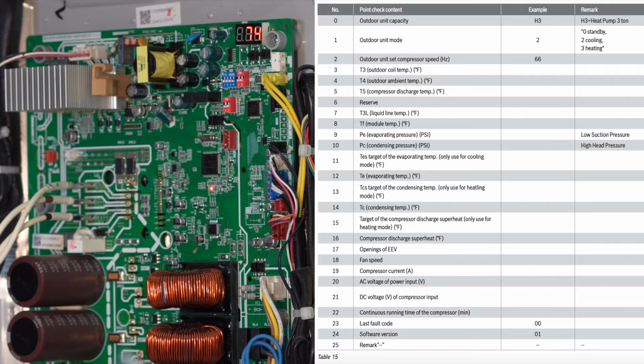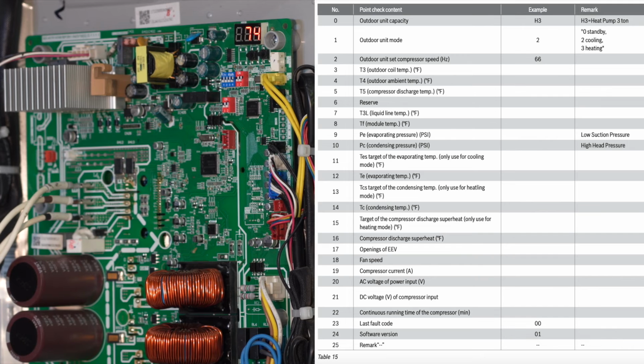Wow. 23 is going to be your last fault code. Whatever the last fault code was, it's going to hold it in memory pretty much infinitely until it has another fault code. Exactly. And then 24 and 25. 24 is a software version, that's not really that important to you guys. And 25 is another one like number 6 up there that's not actually being used.